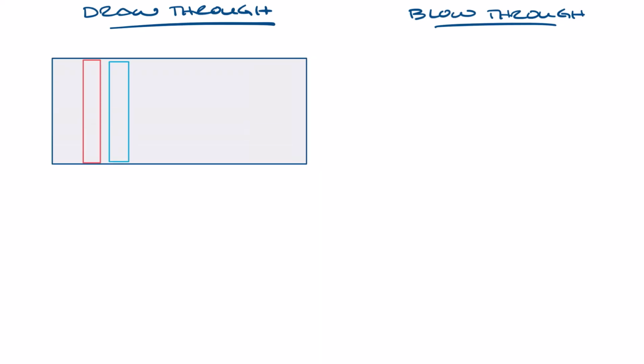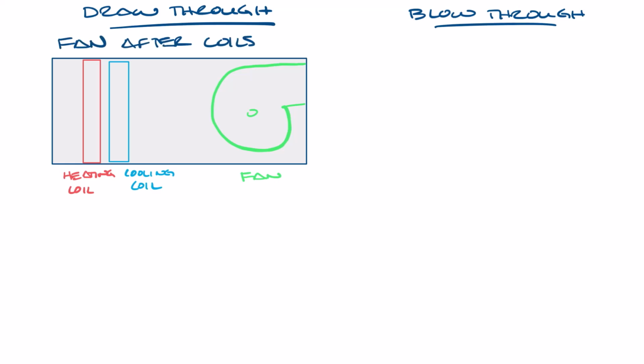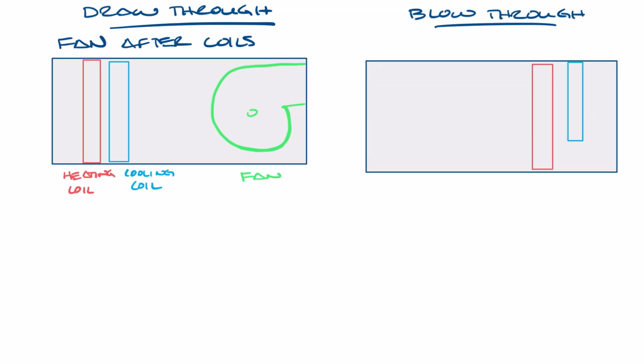In an air handler, you have a heating coil, a cooling coil, and a fan. If the fan is after the coils, it's called a draw-through arrangement because the air is drawn through the coils. And if it's before the coils, it's a blow-through arrangement because the air is blown through the coils. Let's move this up a little and look at this.